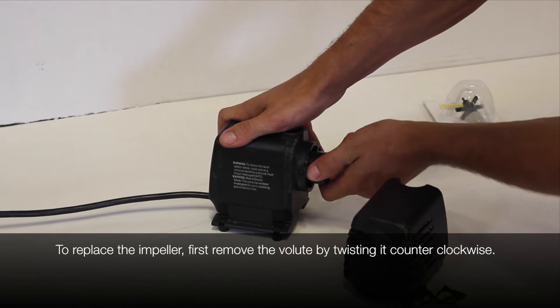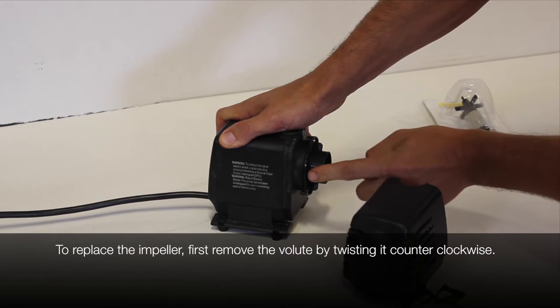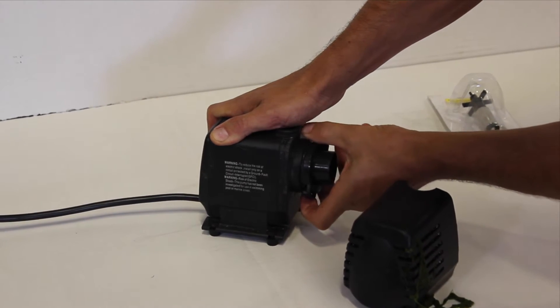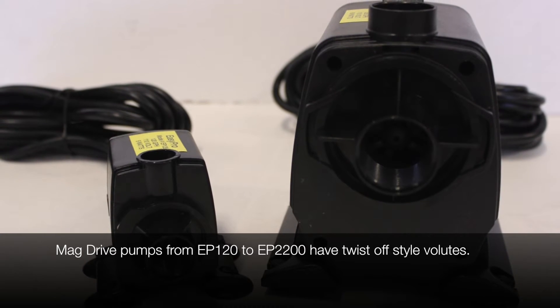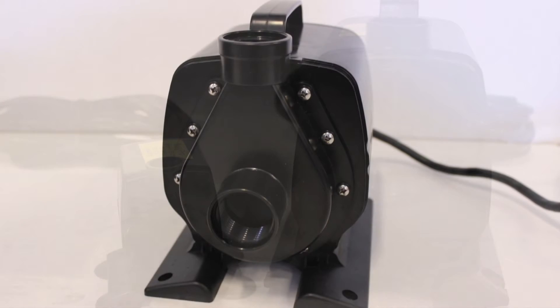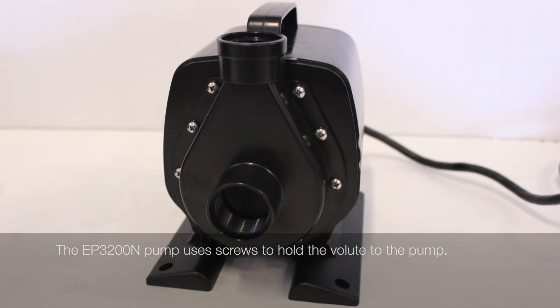To replace and inspect the impeller, first remove the volute or impeller cover by twisting it counter-clockwise about a quarter turn until the connection tabs are clear. EasyPro MagDrive pumps from the EP120 to the EP2200 have twist-off style volutes. On the EP3200N you'll need to remove the screws on the volute.